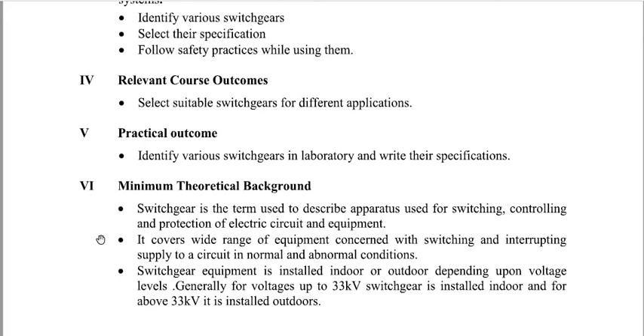Switch gear equipment is installed indoors or outdoors depending upon the voltage levels. Generally, for voltage levels up to 33 kV, switch gear is installed indoors, and for voltages above 33 kV it is considered as outdoor installation. These are the important points to understand the content.